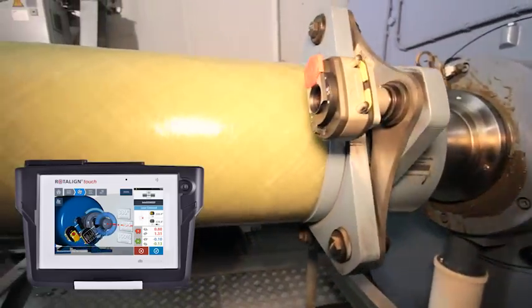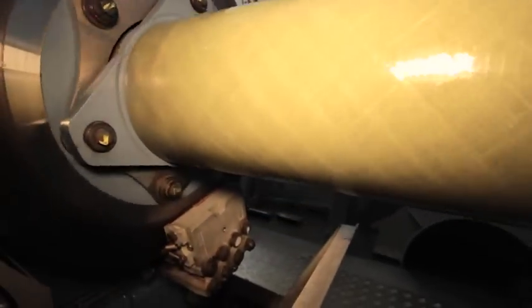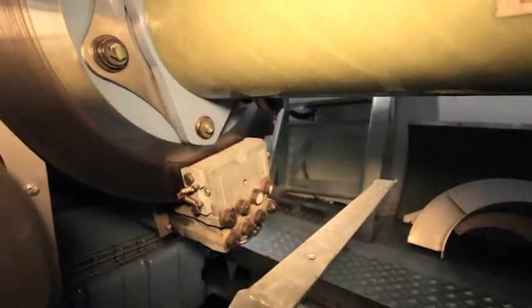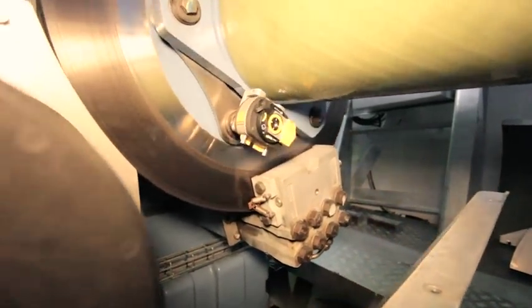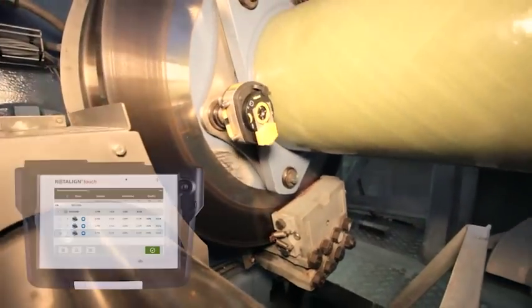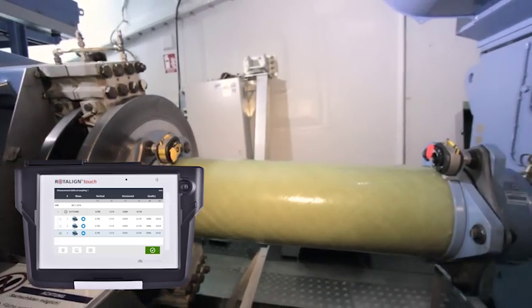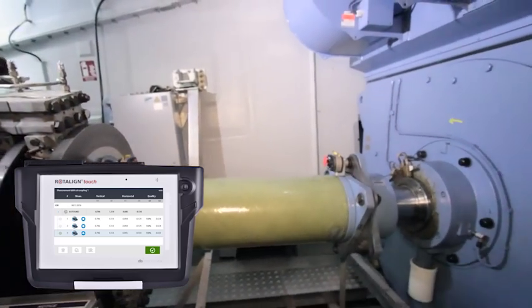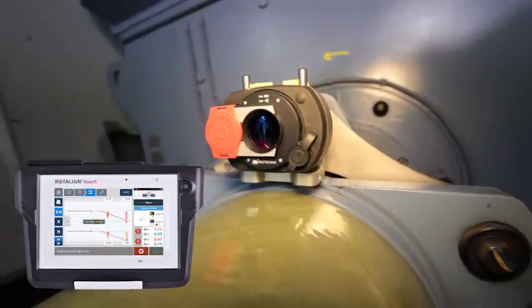The intelligent measuring process collects a large amount of measurement data during the rotation and eliminates low-quality measurement points taken during strong acceleration or deceleration. The individual measuring cycles and the calculated coupling results are compiled in a table for a quick overview of repeatability. Aligning the generator with Rotalign touch is easy as well.